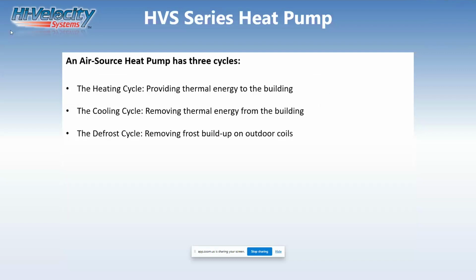Now, an air source heat pump has 3 cycles. It has a heating cycle, providing thermal energy to the building, a cooling cycle, removing that thermal energy out of the building, and a defrost cycle. What do you mean by defrost cycle? Well, on a cold day, that unit will defrost. It'll drop moisture out of it. And you've heard both Jordan and Don talk about it. That's important to understand what happens on a defrost cycle. If it goes on a defrost cycle, that means you're not getting heat out of the heat pump.